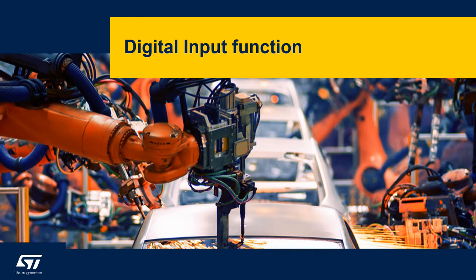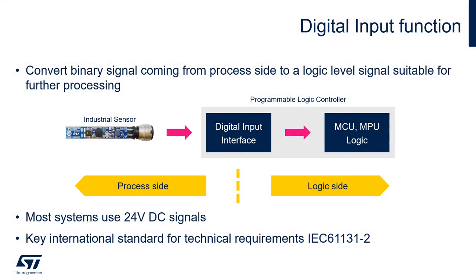Let's review what is the main function and what are the characteristics of a digital input. The key purpose of the digital input interface is to convert binary signals coming from the process side to the logic level signals on the right side. Typically, a signal with two levels and a nominal magnitude of 24V DC comes to the PLC digital input periphery, where it is evaluated and translated to 3.3V, eventually to 5V logic levels, and then further processed by MCU or some other application-specific circuits. Several characteristic types have been specified in the IEC 61131-2 standard to ensure compatibility between external signal sources like industrial sensors and the input interface.